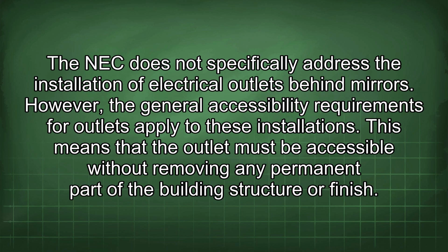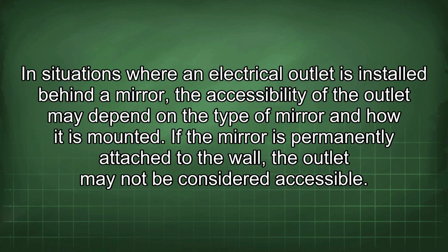However, the general accessibility requirements for outlets apply to these installations. This means that the outlet must be accessible without removing any permanent part of the building structure or finish. In situations where an electrical outlet is installed behind a mirror, the accessibility of the outlet may depend on the type of mirror and how it is mounted.